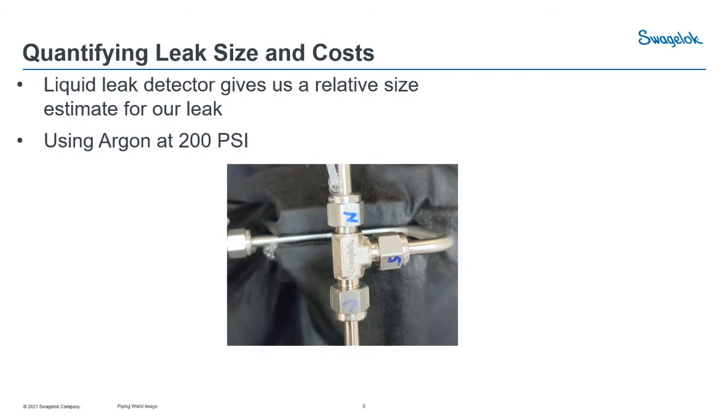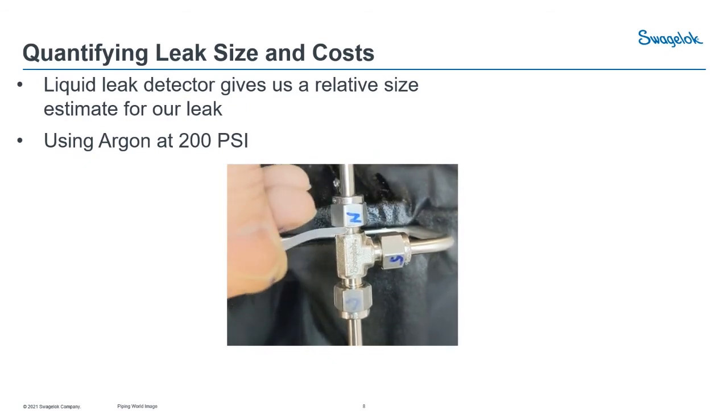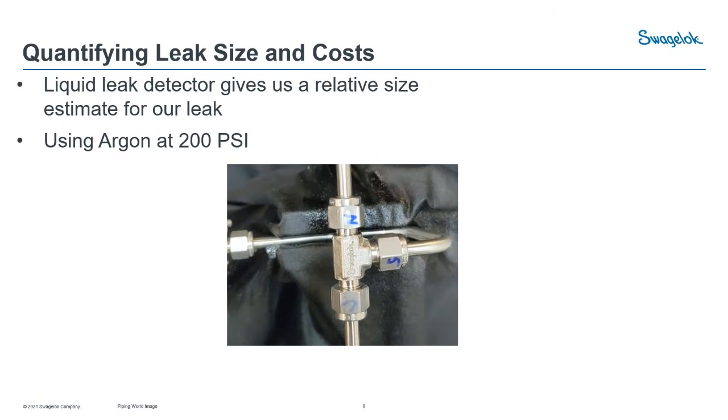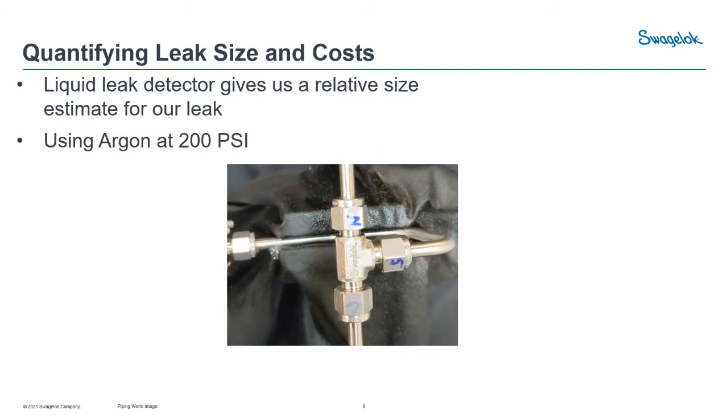I want to take one last shot. You can see some of our leak in the background there, but this is more to show what it looks like when you don't have a leak. I figure we should also show the positive side. A leak-free fitting should just run off just like water. Now, at times you can get a little bit of foaminess with the Snoop if you shake the bottle up or something.